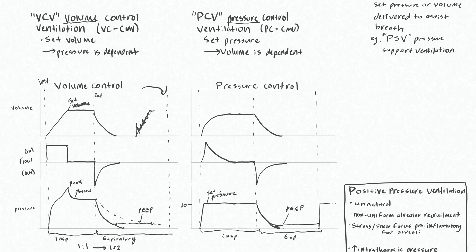Your peak inspiratory pressure during pressure control mode is whatever you have your pressure set to — but only if you don't have any PEEP. If we started from zero and set inspiratory pressure to 20, our peak pressure is 20. But if we add 5 of PEEP between breaths, we now have a starting pressure of 5. So with that same inspiratory pressure of 20, our resulting peak pressure — the total airway pressure during the inspiratory period — will actually be 25 instead of 20.